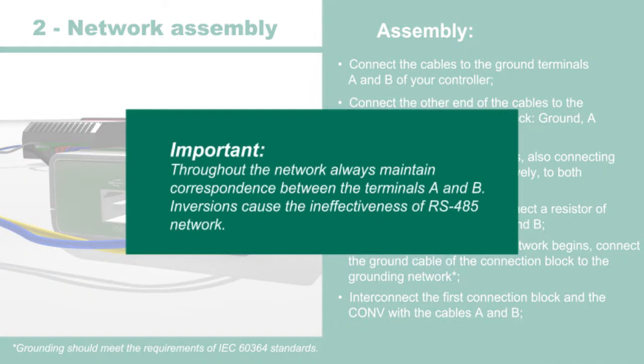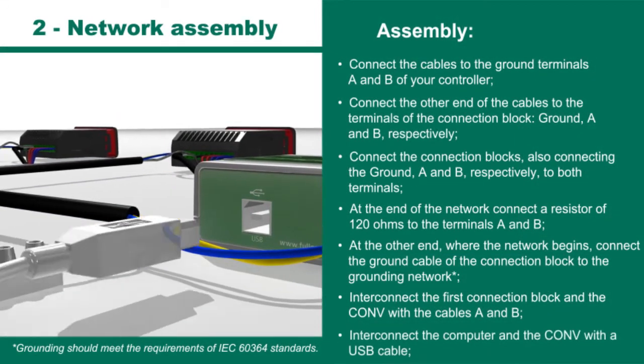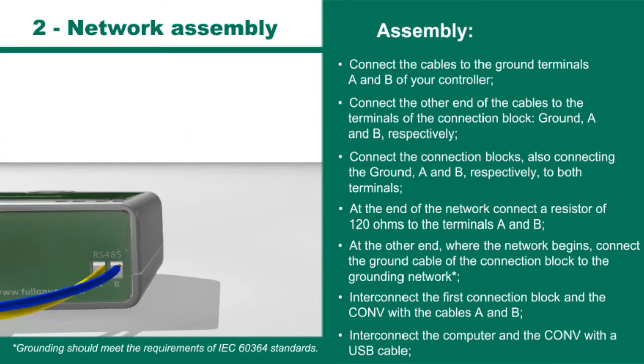Important: throughout the network, always maintain correspondence between the terminals A and B. Inversions cause the ineffectiveness of the RS485 network. Interconnect the computer and the conv with a USB cable.